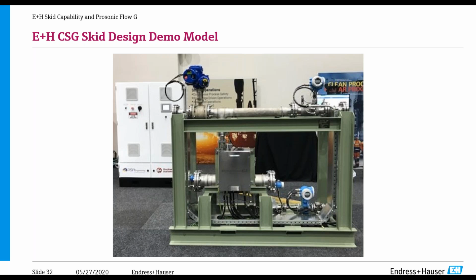There is an IECEx certified assembly. So all the equipment on the skid has IECEx certification. The skid is inspected in accordance to AS 60079, so fully in compliance with hazardous area requirements of Australia. Once the skid is installed, there's a requirement for an HA audit in some states in Australia, and this is a service that we can assist with as well.